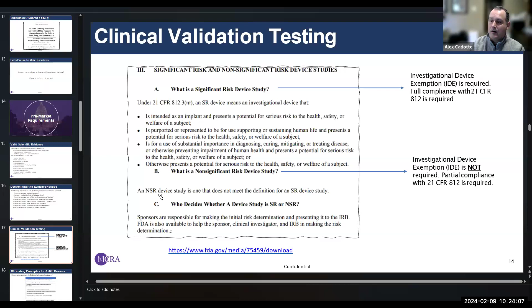So generally speaking, when you're performing this testing, a question that might come up is, do I need an IDE from FDA, which is an investigational device exemption? It basically means that you can distribute your device to the places where you are doing your clinical research. For significant risk studies, where you're talking about things like an implantable device, FDA expects to review your testing before you subject patients to those risks. A lot of digital health devices don't actually make contact with the patient. A lot of times they're diagnostic, and your study can be done on retrospective data. So that's one of the convenient things about AI machine learning devices, especially in the diagnostic space: an IDE isn't necessarily required. That's something I'm not going to be able to get into a lot of depth on.